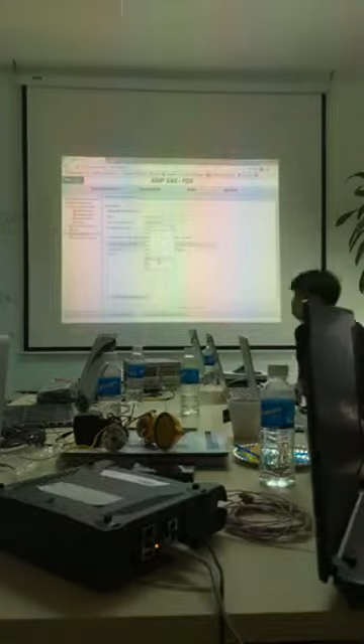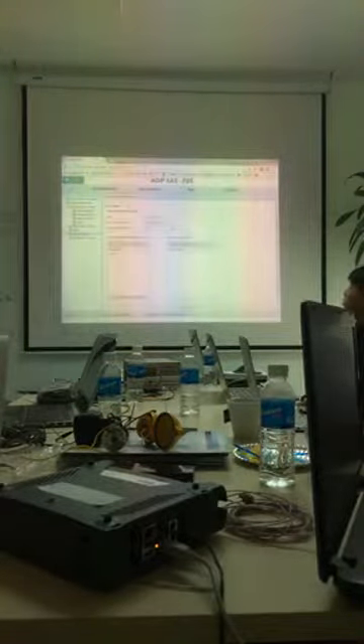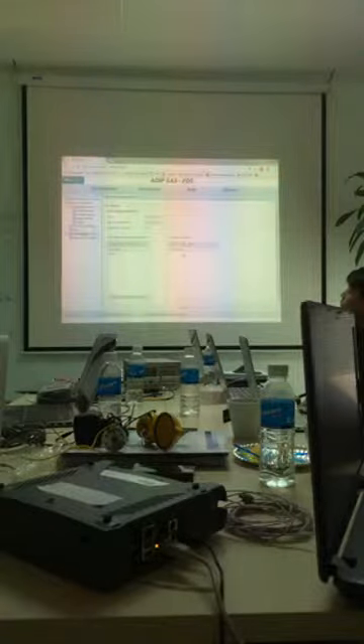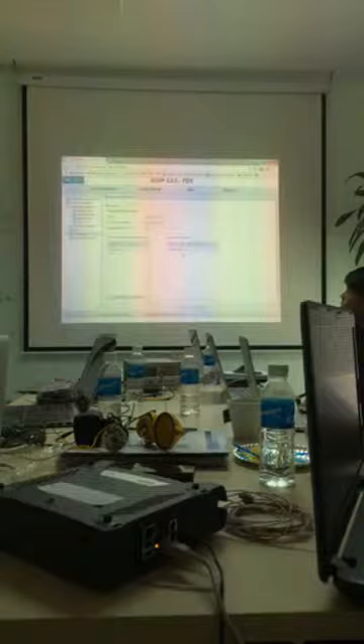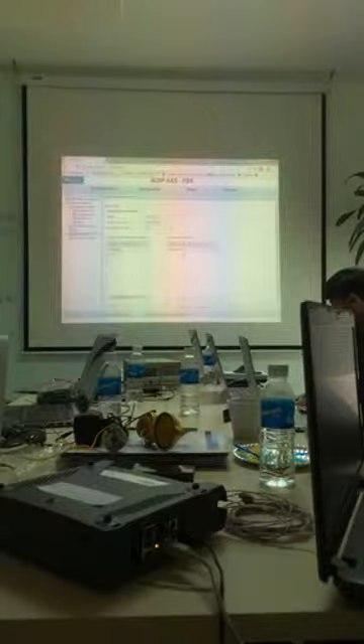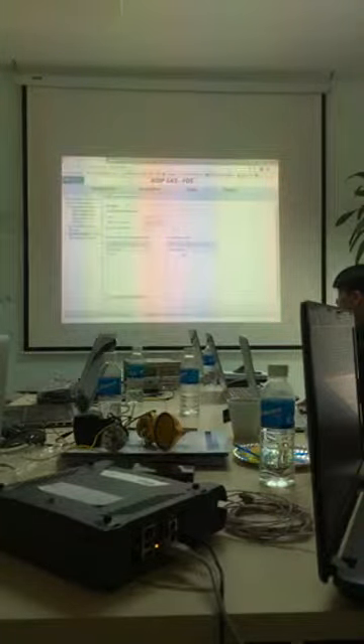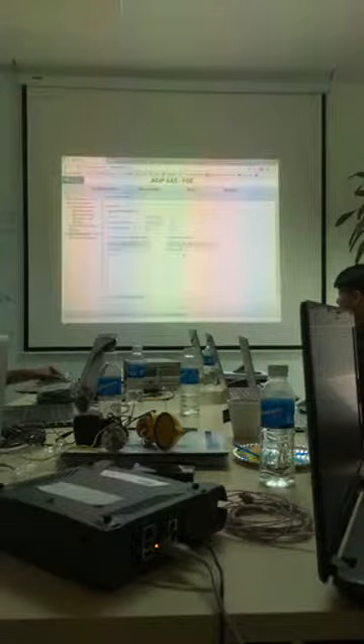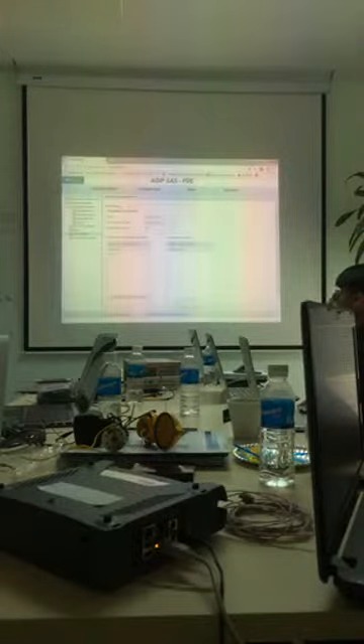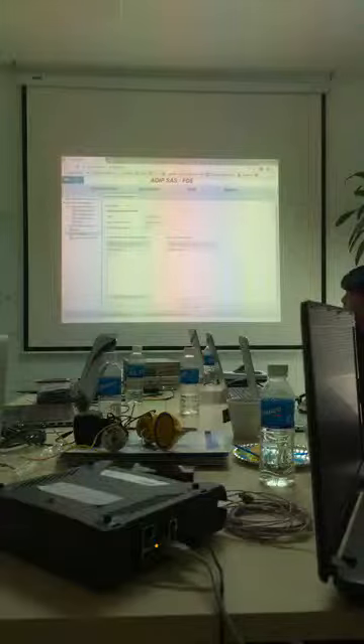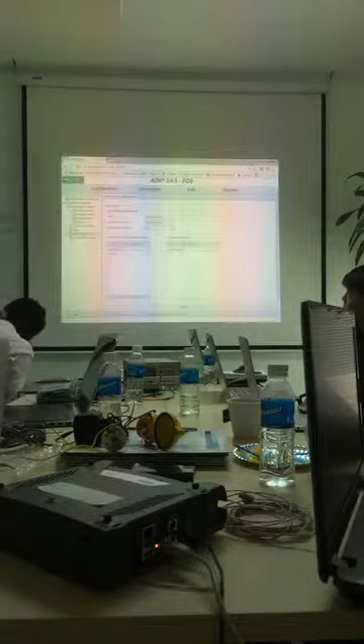So as one of the options, most of the time we put a relay. If you are connected to any internet server, if you are connected through an Ethernet cable to your company and there is Ethernet access, you can put in an email address. And when you reach the level, the guy will receive an email. And in the email, it will be written: alarm group 1, temperature out of limits.